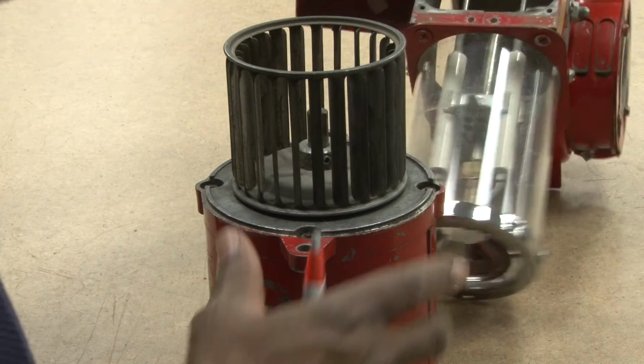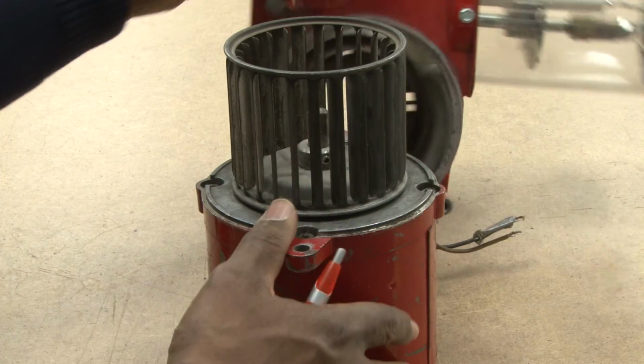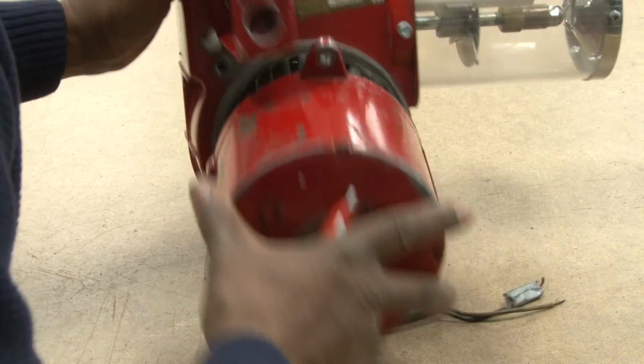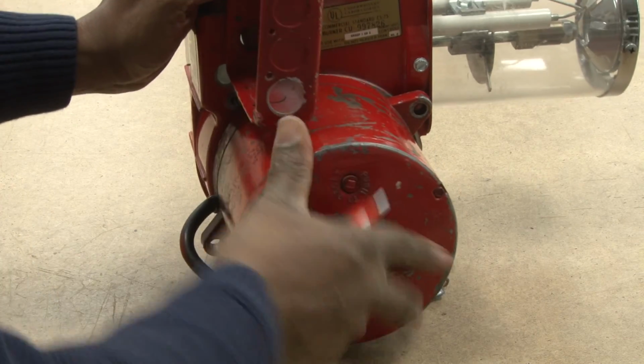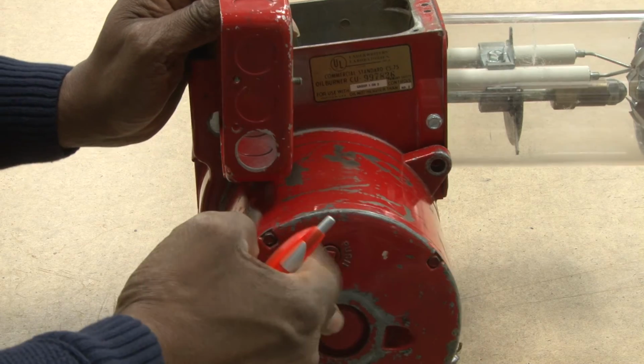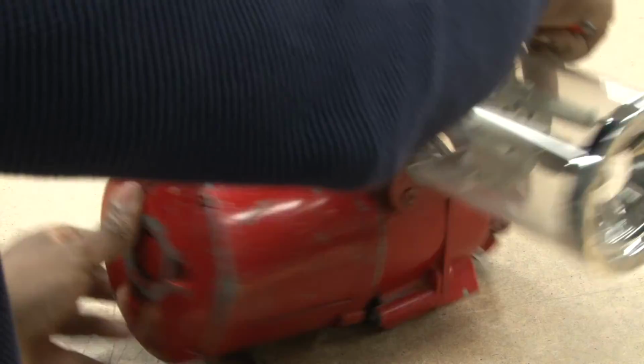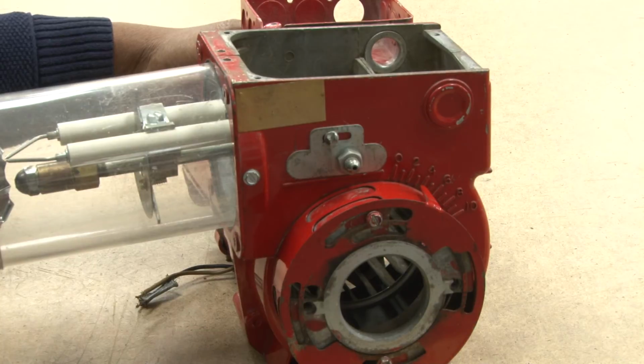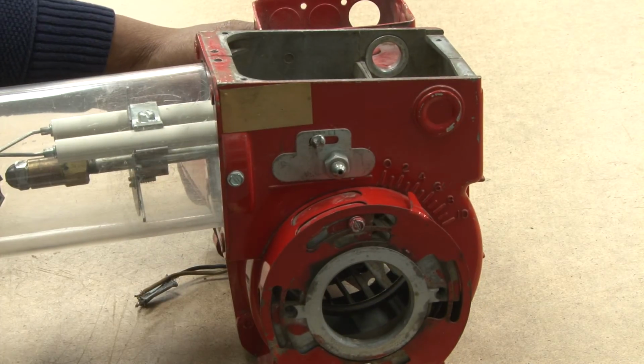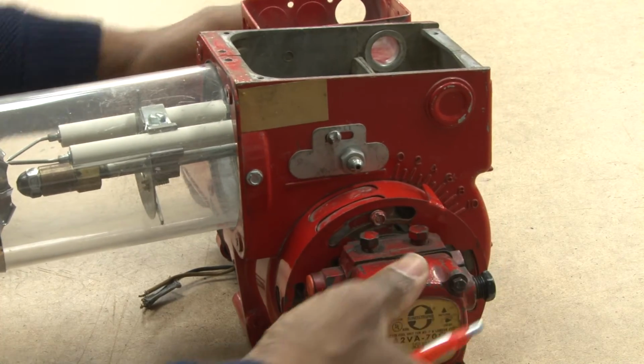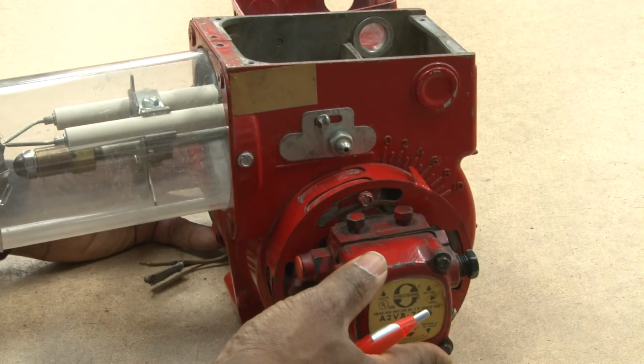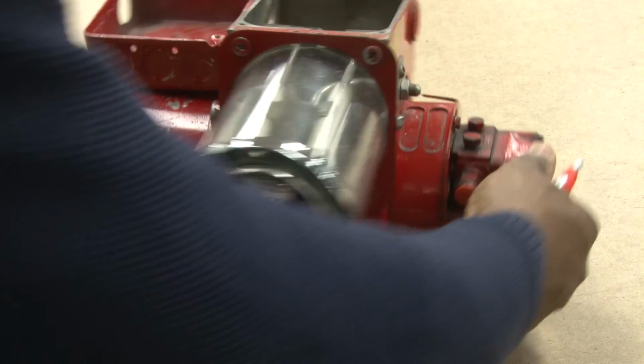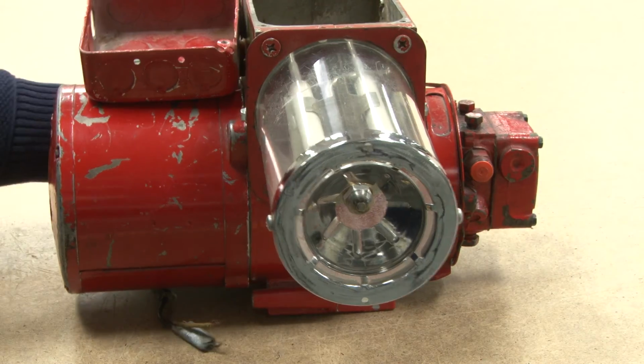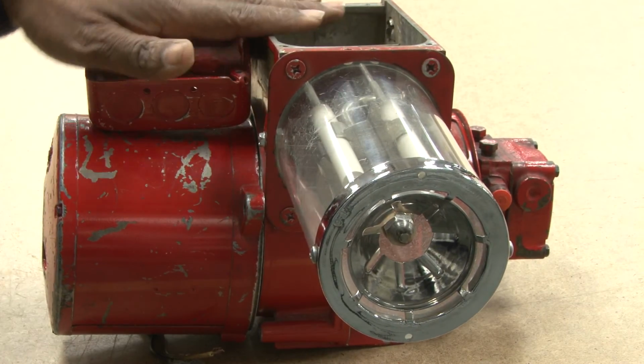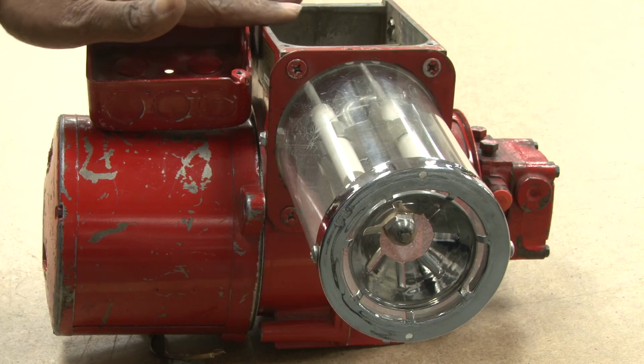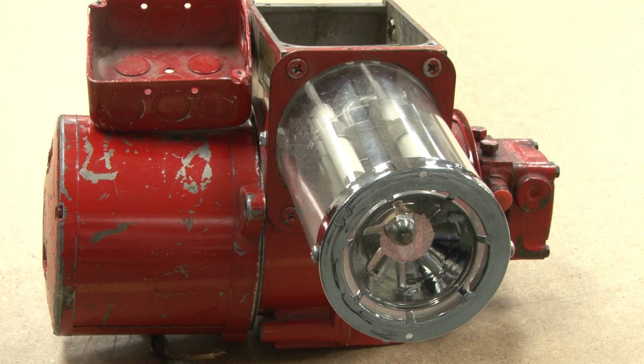So if we were going to join this together, we would take the blower assembly, connect it to the housing, take a coupler, go through this, then connect it to the pump. And that's pretty much the operation of the oil burner. And on top of this will be the transformer to generate the high voltage for operation.